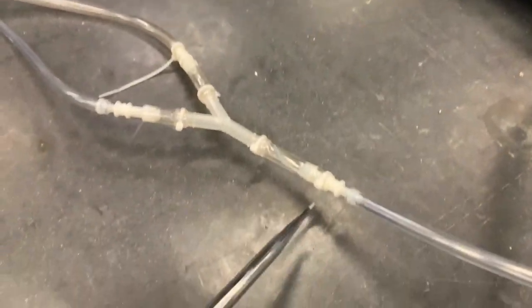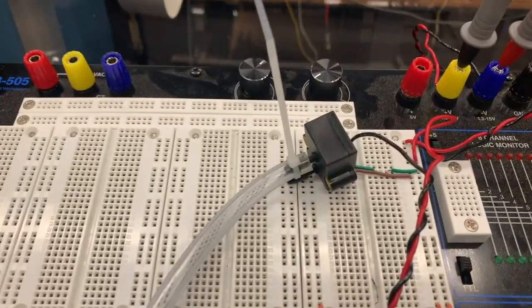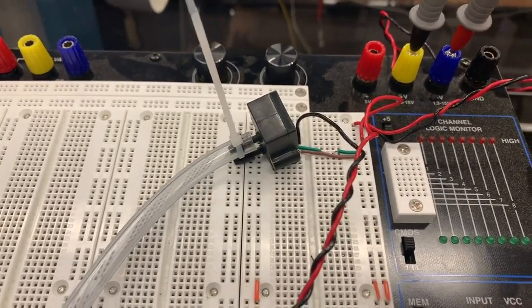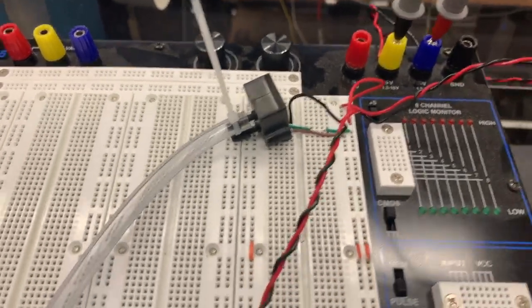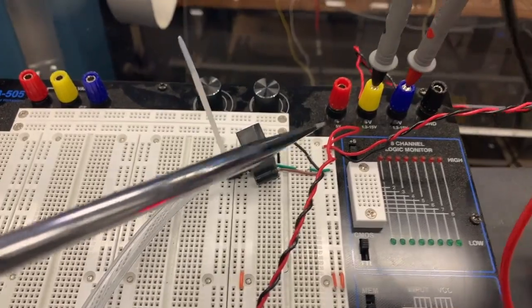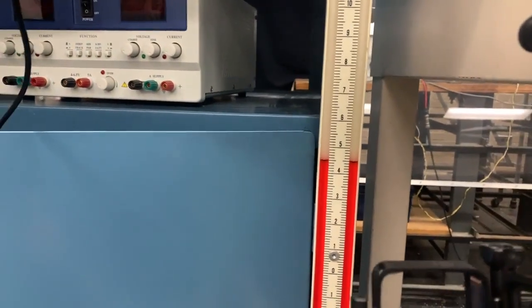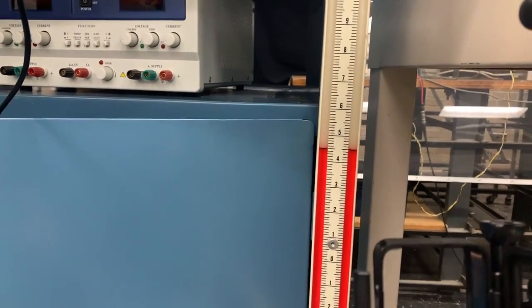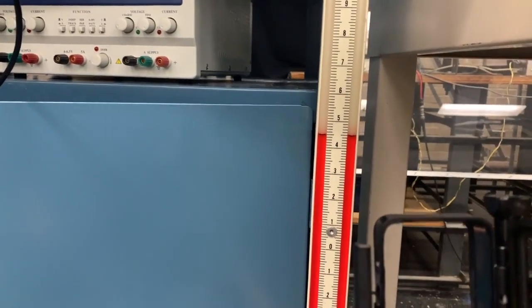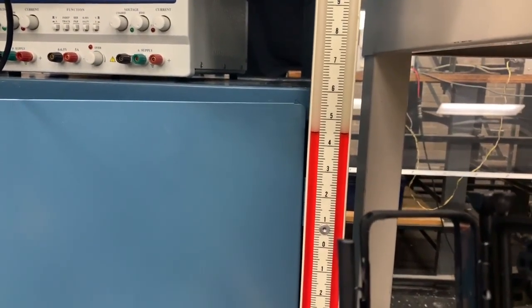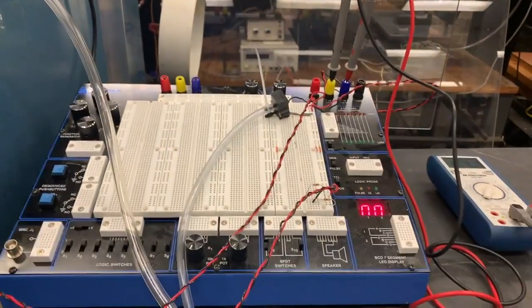So this is the total head, duplexed into a Y. With some really fine work on the zip ties, we've got one pressure tube going into the total or gauge pressure port of a PX138 pressure transducer, and I'll supply a wiring diagram for this one. Then we have the other pressure tube, split at the Y, going into a manometer. You'll note it's graduated in inches and decimal inches, and the case to the right is where you'll see the camera that will be looking at the manometer during the setup.